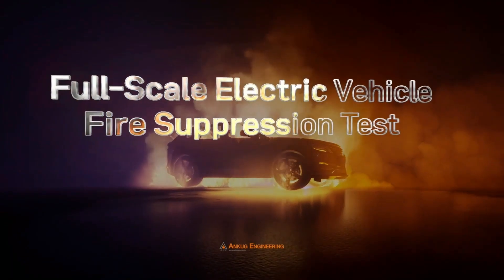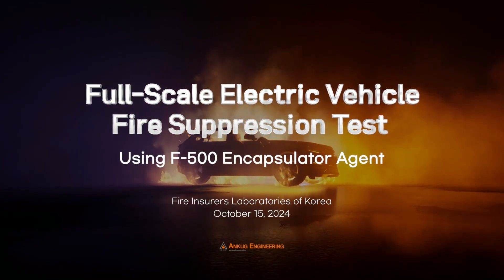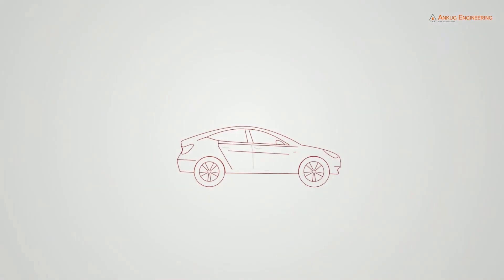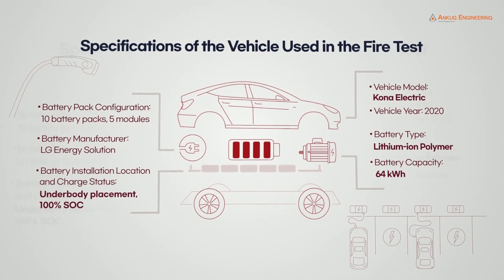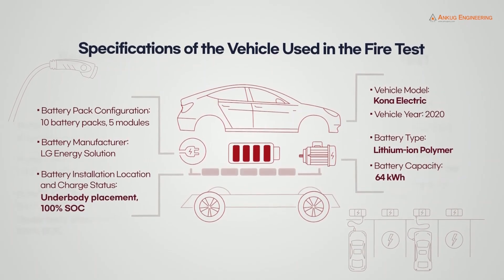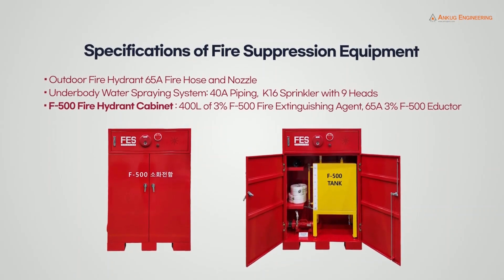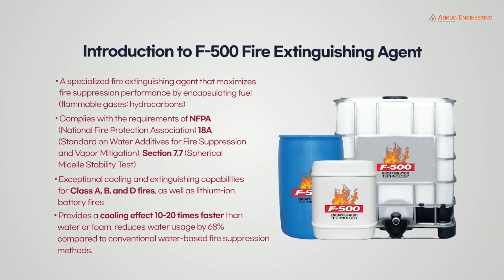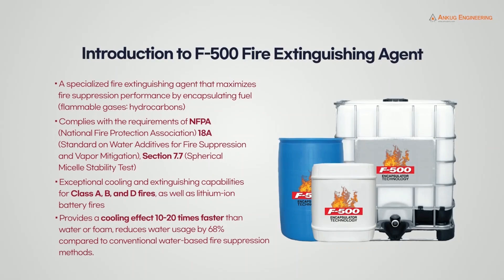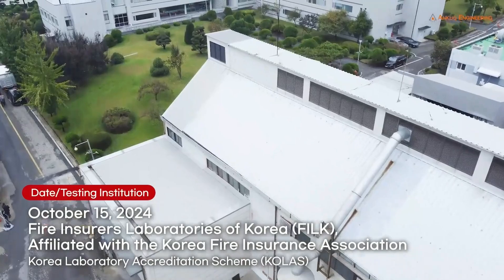On October 15th, 2024, F500 Encapsulator Agent was put to the ultimate test. The 2020 Hyundai Kona Electric used contained 10 battery packs at 100% charge. Fire suppression was applied by an underbody water spraying system supplied by an outdoor hydrant. An F500EA solution proved to absorb thermal energy 10 times faster than plain water or foam. This test took place at the KOLAS Accredited Fire Insurers Laboratory of Korea.